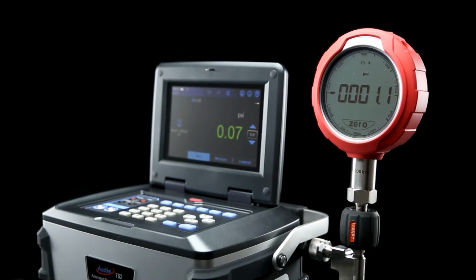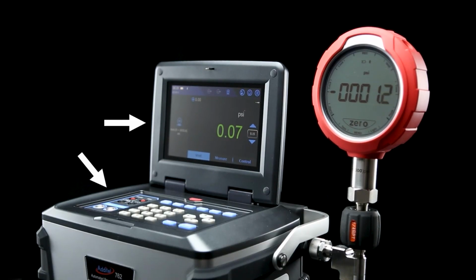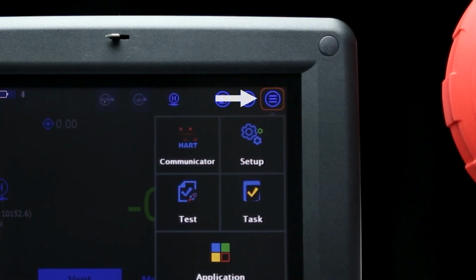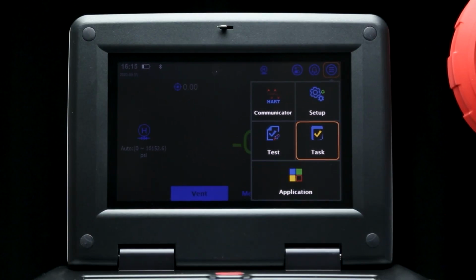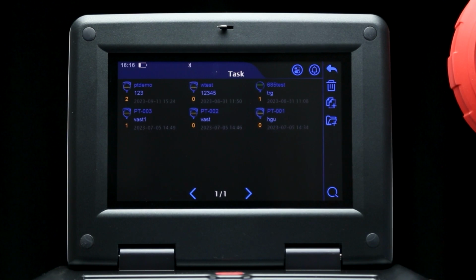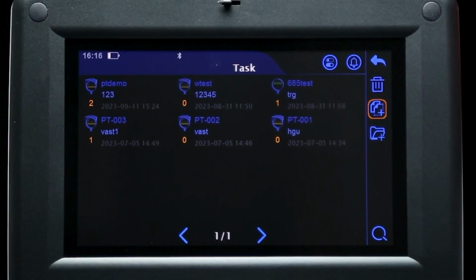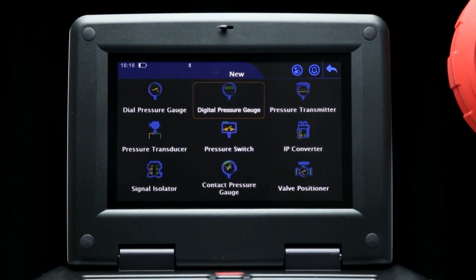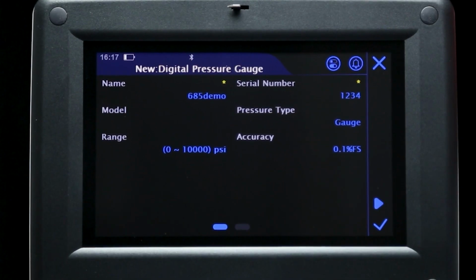Now that the gauge is connected, use the touchscreen or keypad to select the menu in the top right corner of the display. Then select the task function. From here you'll see the task library of all of your previously saved devices. Select the New Device button on the right-hand side, and select the type of device, in this case a digital pressure gauge. In the next screen, details about the task can be entered.